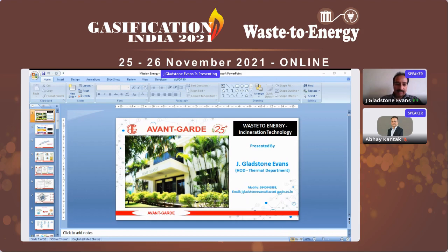Then waste to energy configuration: whether to go for a one boiler, two boiler, or three boiler configuration depends on the capacity. If it is less than 850 TPD, we can go for one boiler, 1 TG configuration. But one disadvantage in going for one boiler, 1 TG is that once in 3 months, you have to shut down the boiler for cleaning. At that time, you cannot dispose of the waste, so the whole plant will be under shutdown. When we go for two boiler, 2 TG configurations, the boilers can be planned in a staggered way so that at least 50% of the capacity will be available to dispose of your waste.